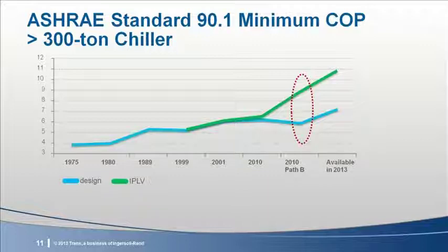We see that required chiller full load efficiency flattened out, but there are more efficient chillers that can be selected. The last set of data are premium efficiency chillers, one selected for very high full load performance and the other selected to result in a high IPLV. So additional chiller efficiency levels are still available. In fact, over 20% higher full load or IPLV. Now, to further improve system performance, practitioners have looked to different components in the chilled water system, the pumps and the cooling tower fans. Now, before tackling system interaction, let's look at the chilled water system components historically.